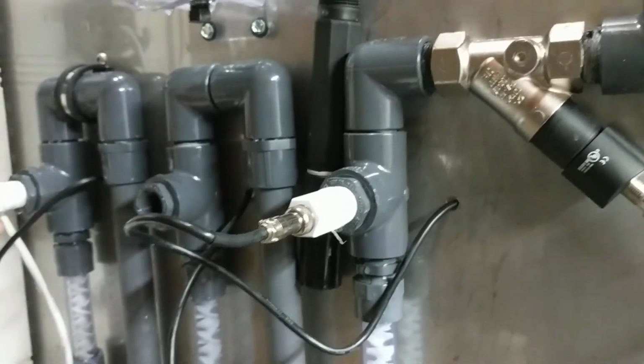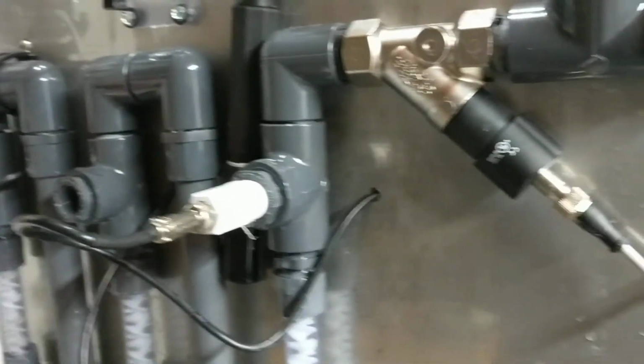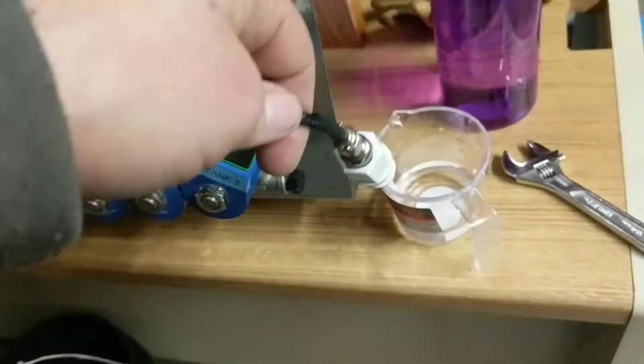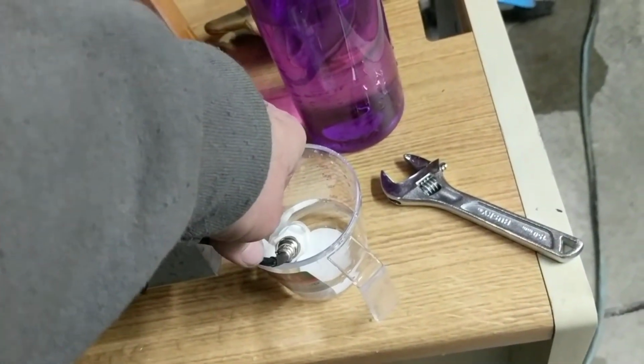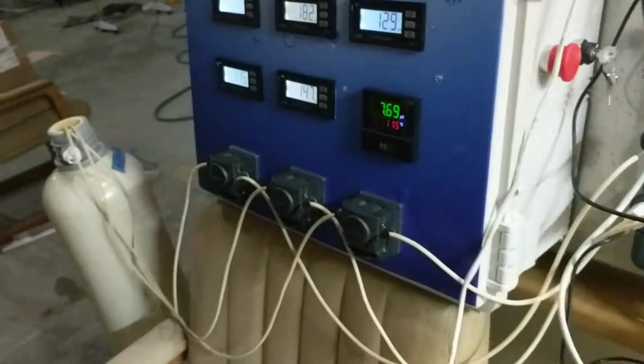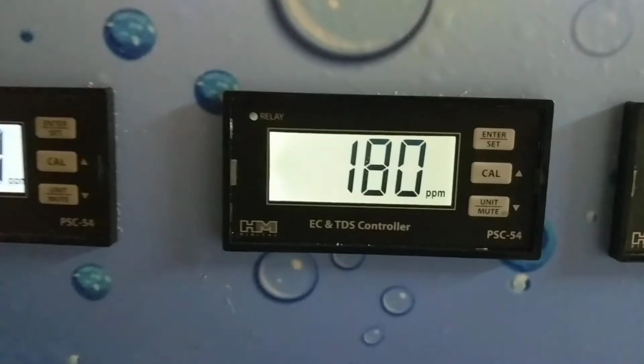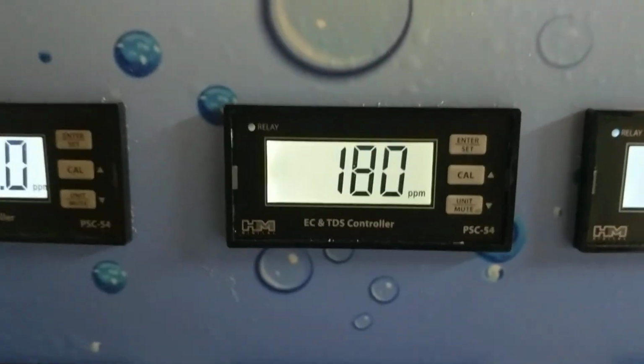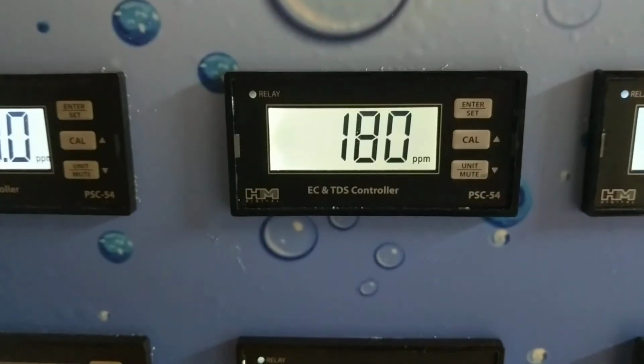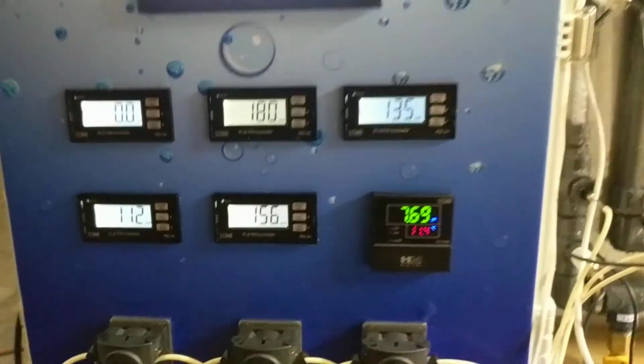So I'm going to take out the old sensor and put it in there for a second just to hold it while I put the new one in. New sensor is in, and this one is at 180, so I'm off by about 8 TDS right there. So definitely got to calibrate that.